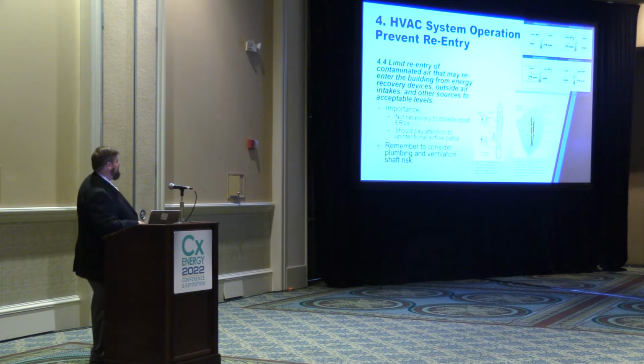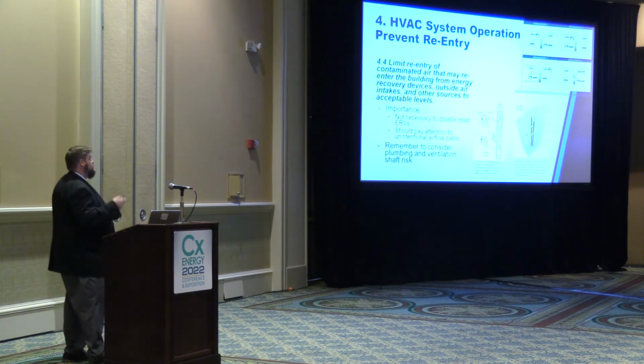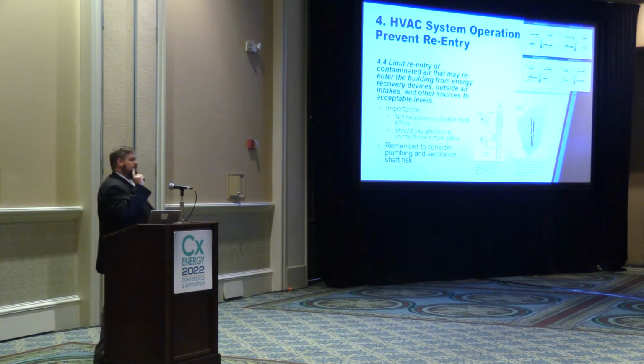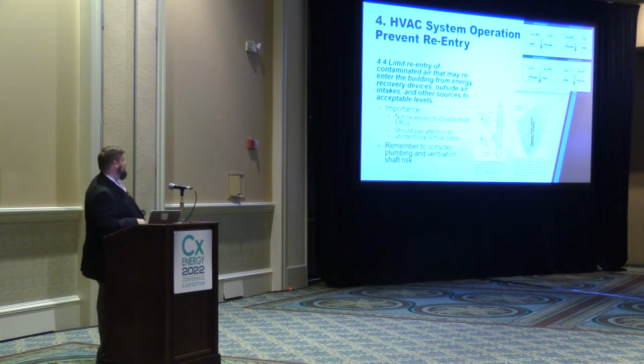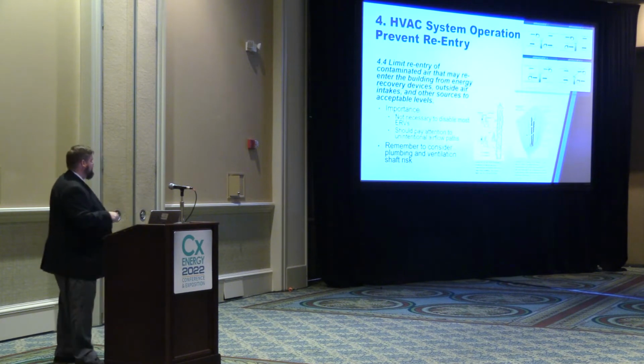TC 5.5, the air-to-air or energy exchange committee for ASHRAE, came back with one sentence: if your wheels are well-designed and well-maintained, leave them running. We said, well, what's well-designed and what's well-maintained? So that one sentence turned into 29 pages showing you where to take pressure drop readings on the different sides of the wheel to figure out if leakage is acceptable, and in reality, fix it.